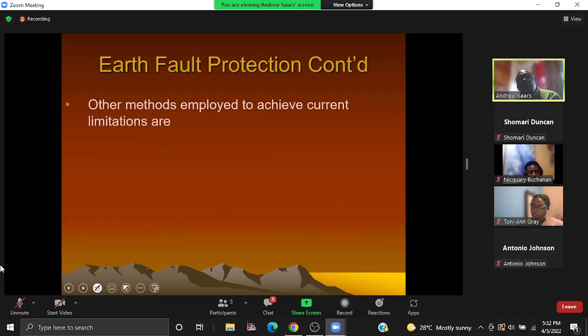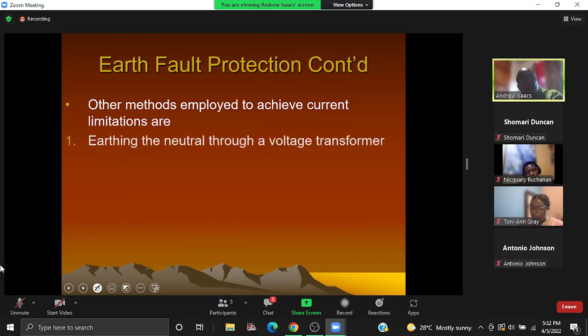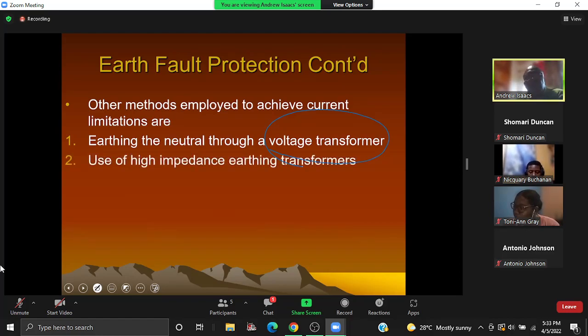Okay, so the other methods that are employed to reduce this current, because remember we are protecting this generator, would be to earth it through a VT. We have already established that VTs are expensive. There are also some other electrical issues with using VTs, and we'll just mention them quickly. So one method is earthing through a VT. Or secondly, using a high impedance earthing transformer. And this is the one that we are going to be focusing on. So, earthing the generator through an earthing transformer.